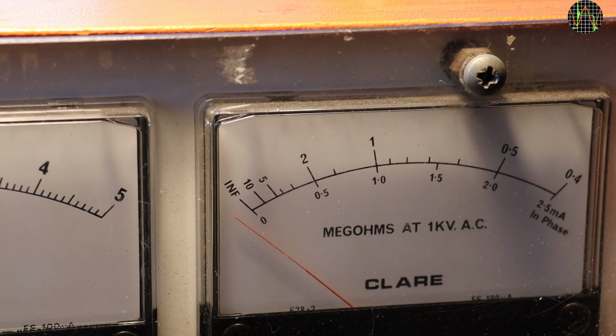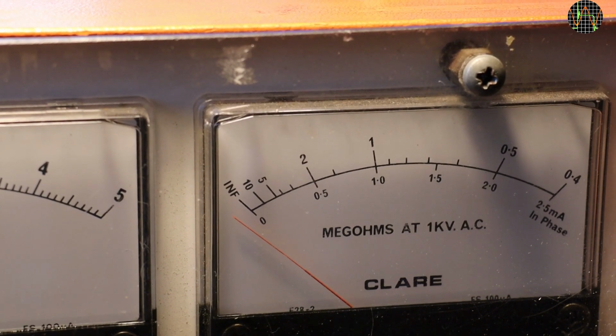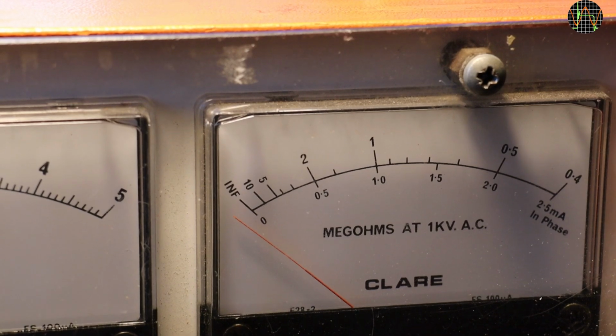The reason the upper scale says megohm per kilovolt is that the megohms are obviously depending on the set voltage. At 1 kilovolt, a resistor of 1 megohm passes a current of 1 milliamp, which explains how the scale was drawn. At 5 kilovolts, the same 1 milliamp means a resistance of 5 megohm, so one has to multiply the megohm with the kilovolt number. A reading of 10 at 5 kilovolts means 50 megohm.